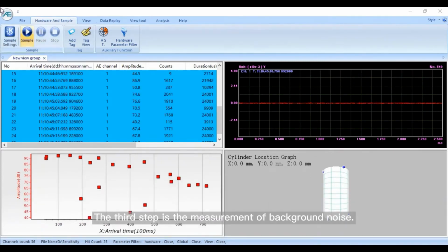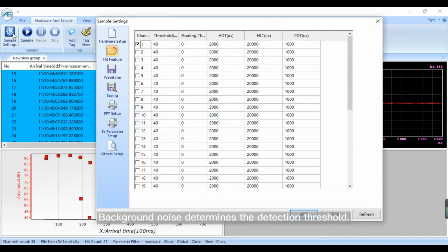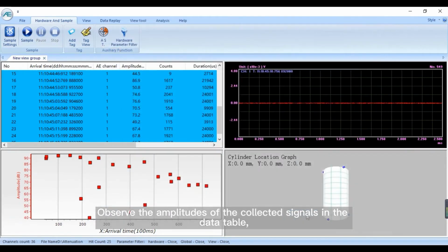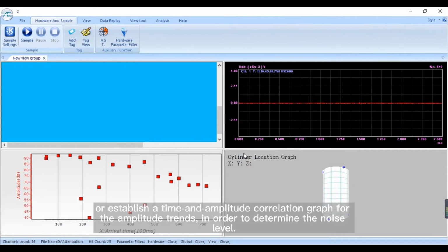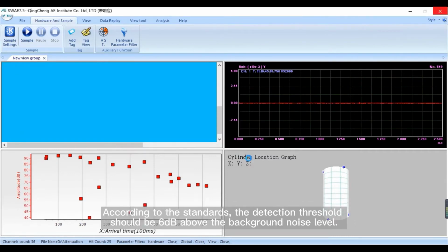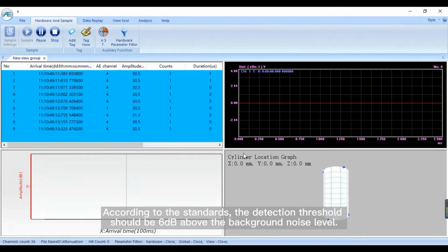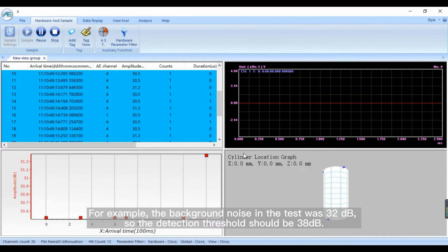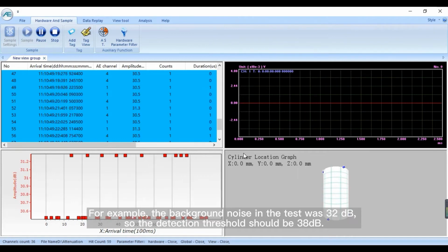The third step is the measurement of background noise. Background noise determines the detection threshold. Decrease the threshold to a lower level, for example 30 dB or lower, and start to collect data. Observe the amplitudes of the collected signal in the data table, or establish a time and amplitude correlation graph for the amplitude change in order to determine the noise level. According to the standards, the detection threshold should be 6 dB above the background noise level. For example, the background noise in the test was 32 dB, so the detection threshold should be 38 dB.